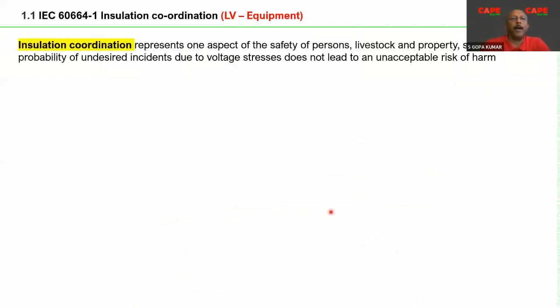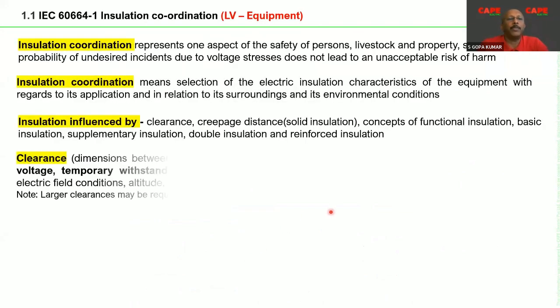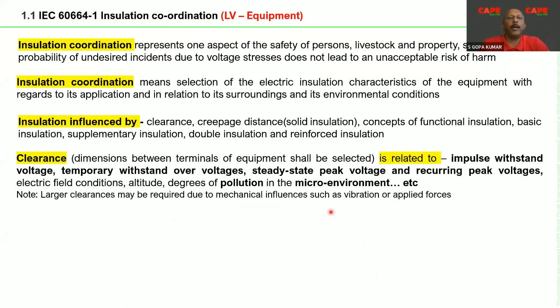How much voltage an equipment can withstand has been included in the subject of IEC insulation coordination. Insulation coordination, I don't want to read it. Probably once you look at the video, you'll be able to understand. So insulation coordination is a subject which talks about how the insulation between two live conductors, or between a live conductor and earth, can be maintained in an equipment, or in an installation, so that maximum life can be expected.